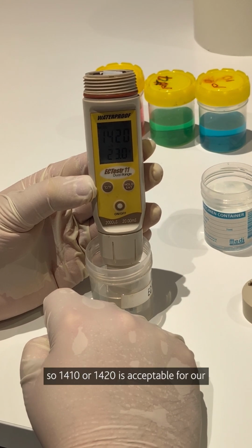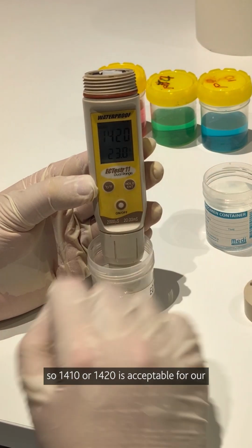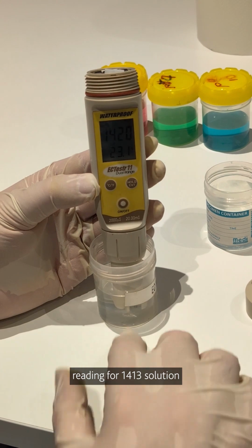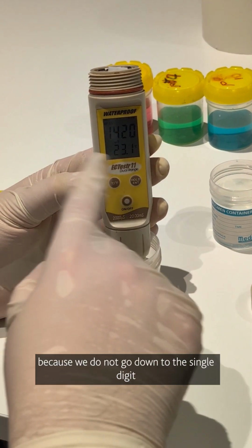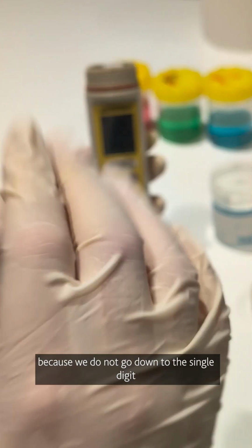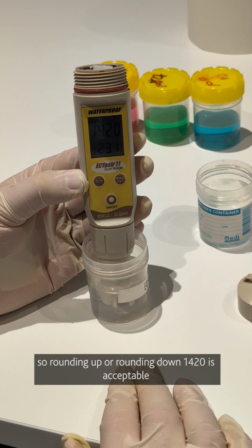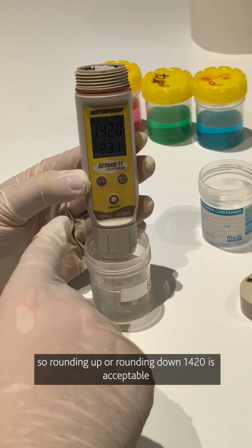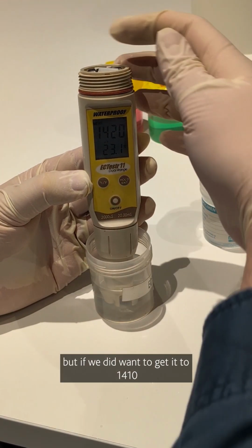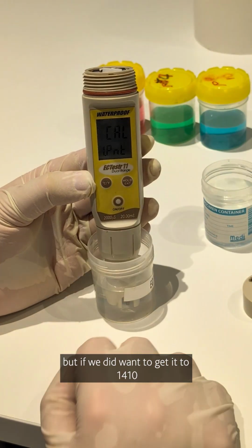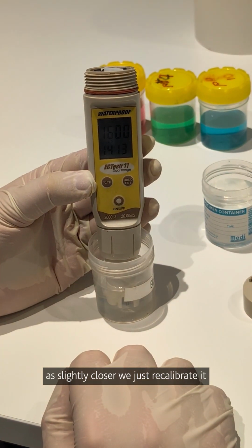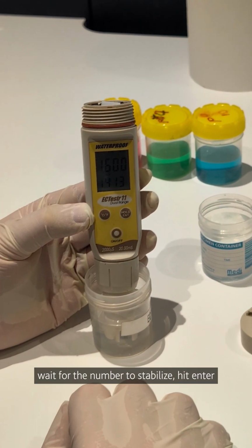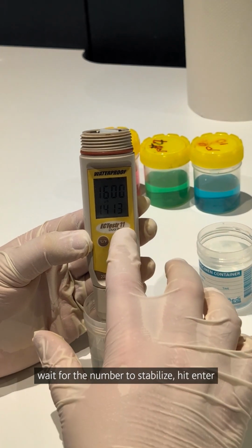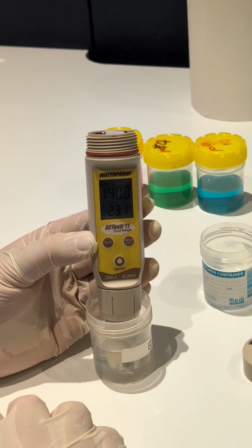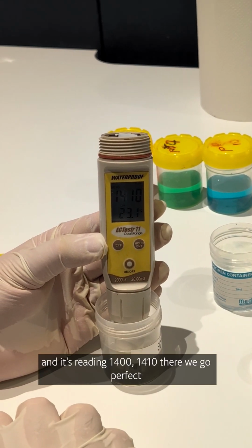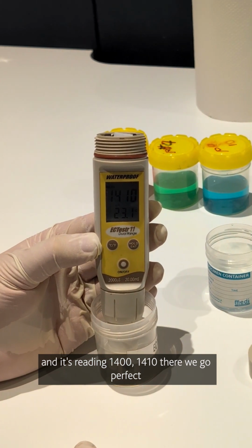So 1410 or 1420 is acceptable for our reading for a 1413 solution because we do not go down to the single digit numbers on these meters. So rounding up or rounding down, 1420 is acceptable, but if we did want to get it to 1410 as slightly closer, we can just recalibrate it. Wait for the number to stabilize, hit enter, and it's reading 1400. 1410, there we go, perfect.